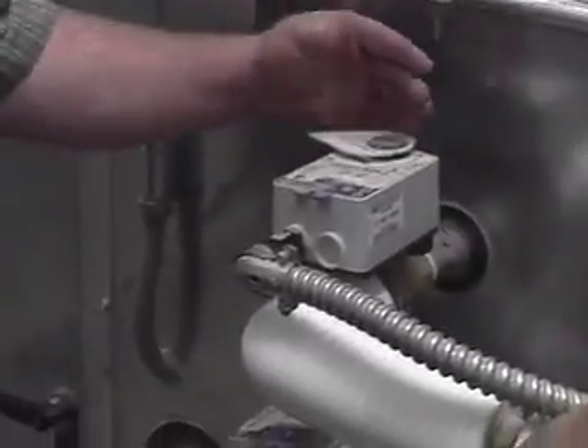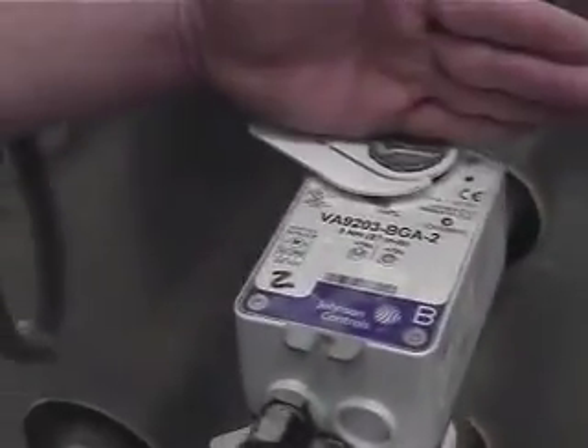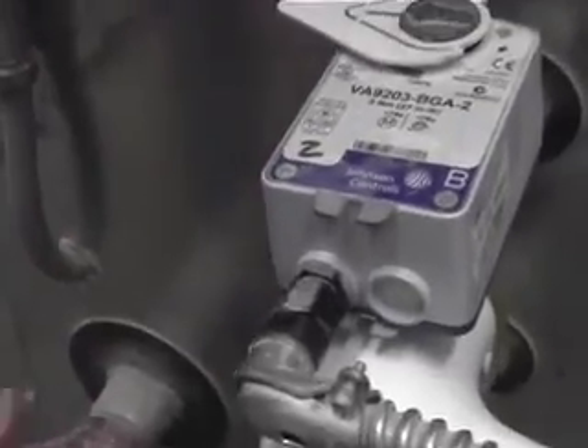My question is, if we were to come in here, how would we know, how can we tell that the pads are calling for the cooling, for the pads to get wet? So the easiest way, without looking at the building management system on the computer, you would be able to look at these valves. These valves indicate the direction with the arrows. So this is basically shut, shut, and open. Okay. You would see them go the opposite way.